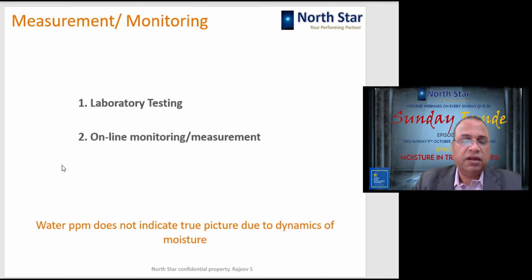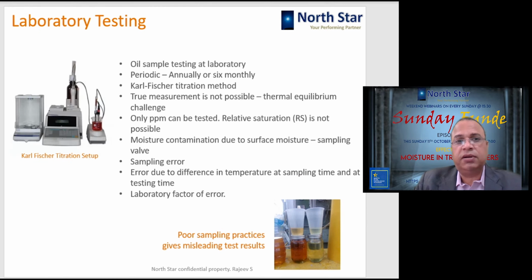Now we are moving towards the second last part of the program, which is moisture management. There are two methods to measure or monitor the moisture. One is laboratory testing and second is online monitoring or measurement. When we are doing laboratory testing, it gives us ppm. We take the sample out of the transformer periodically, maybe once a year, once or twice a year, or maybe once in a quarter. This sample is taken to the laboratory where Karl Fischer equipment is normally used to analyze the water content in the oil, that is ppm in the oil.